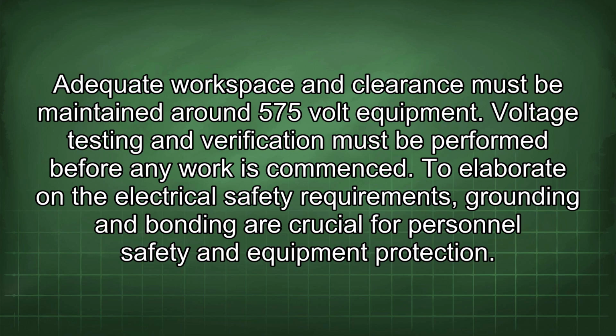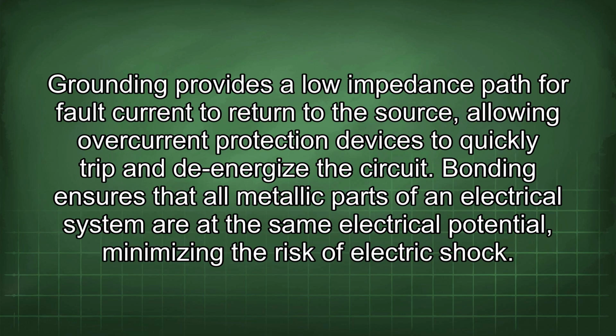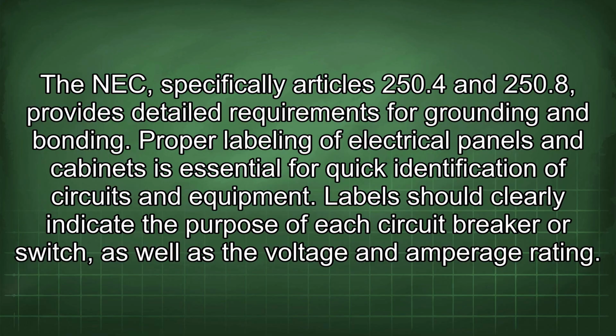To elaborate on the electrical safety requirements, grounding and bonding are crucial for personnel safety and equipment protection. Grounding provides a low impedance path for fault current to return to the source, allowing overcurrent protection devices to quickly trip and de-energize the circuit. Bonding ensures that all metallic parts of an electrical system are at the same electrical potential, minimizing the risk of electric shock. The NEC, specifically Articles 250.4 and 250.8, provides detailed requirements for grounding and bonding.